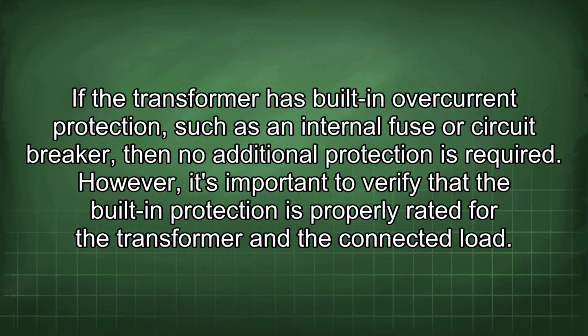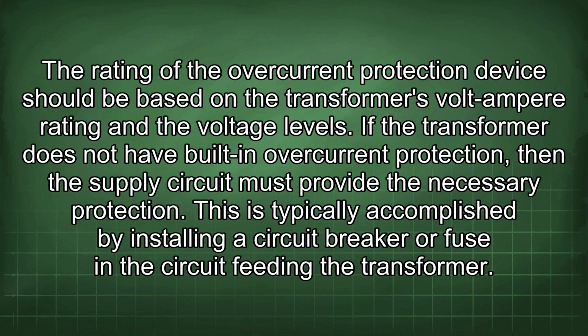If the transformer has built-in overcurrent protection, such as an internal fuse or circuit breaker, then no additional protection is required. However, it's important to verify that the built-in protection is properly rated for the transformer and the connected load. The rating of the overcurrent protection device should be based on the transformer's volt-ampere rating and the voltage levels.